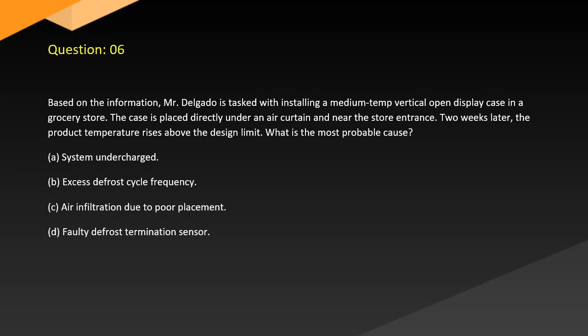Question 6. Based on the information, Mr. Delgado is tasked with installing a medium-temp vertical open display case in a grocery store. The case is placed directly under an air curtain and near the store entrance. Two weeks later, the product temperature rises above the design limit. What is the most probable cause? A. System undercharged. B. Excess defrost cycle frequency. C. Air infiltration due to poor placement. D. Faulty defrost termination sensor.